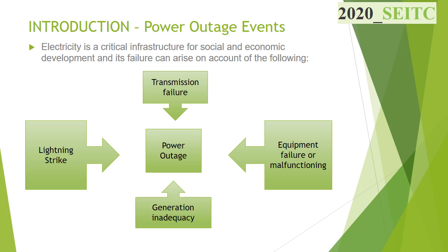Thirdly, generation inadequacy. Overload situation can arise when the power delivery through the transmission line is inadequate for the demand. Protective schemes will operate to relieve the system of overload. Equipment failure or malfunctioning: failure of equipment in service due to faults, fire outbreak, or maloperation can lead to power outage. If not isolated on time, it will create more devastating consequences for the system.